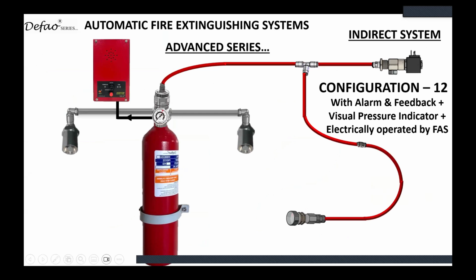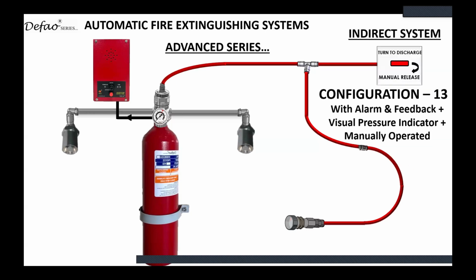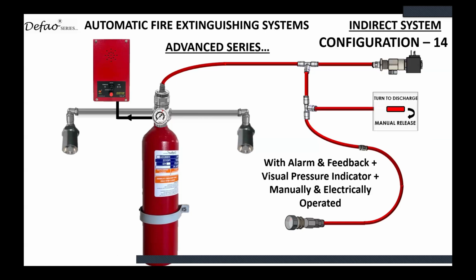And you can also electrically trigger these systems. So in case you are connecting this to your machinery or your electrical system, and you have a process temperature, for example, if the system needs to operate at, let's say, 60 degrees, and you give a 24-volt DC command, we can still operate the system using the electrical trigger also. You can manually release the system also. So these are all the various combinations available.